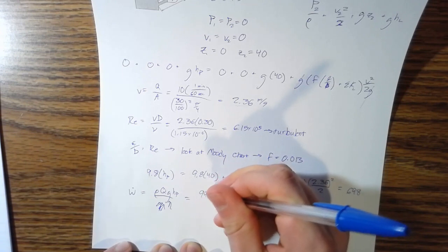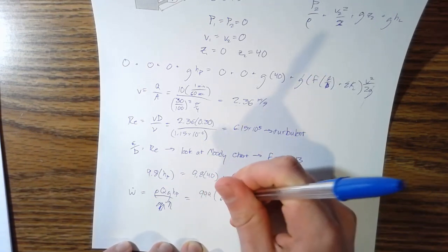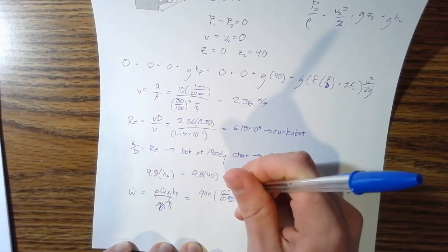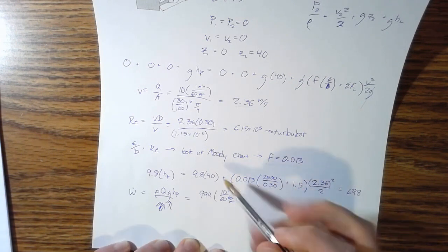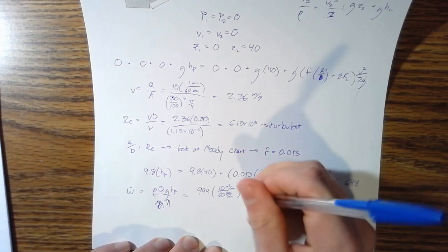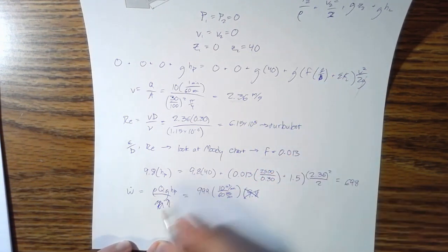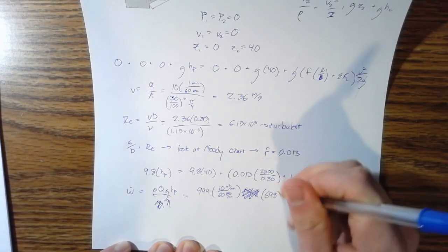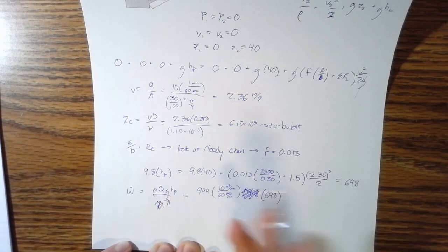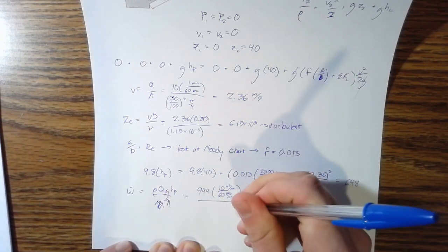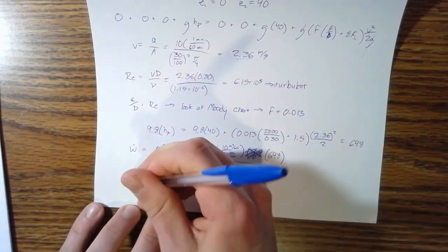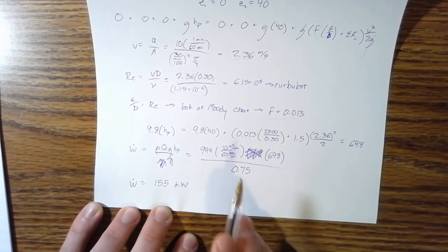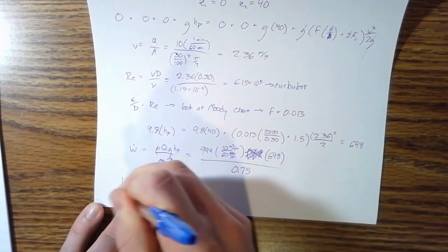So numbers that we're putting in, 999 multiplied by 10. This is seconds per minute. This is meters cubed per minute. So this is just a conversion here. This isn't a new number because this is our flow rate, divided by that to get into seconds. G is 9.8. So G times HP, that's this 698. So we don't have to multiply by gravity there. That's why we left it like that. You could divide by G and then just multiply it again, but not really worth it. And then divide by our efficiency of 0.75. And we should get W dot is equal to 155 kilowatts. The number you're going to get up here is a large number, and that would be in watts, so convert that to kilowatts.